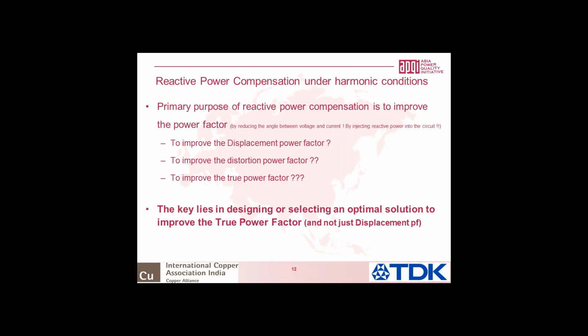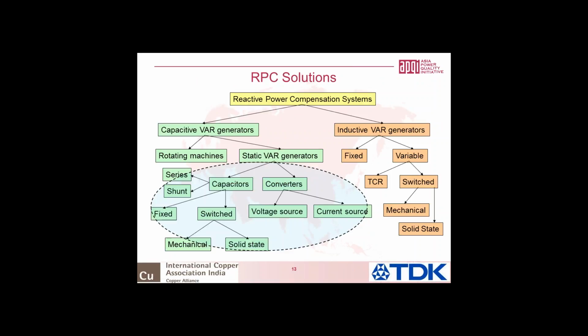As you would see, though they are linked, they can also be to some extent, or to a large extent, independently controlled, the displacement and the distortion power factor. So under harmonic condition, what I would submit, it's not just to improve the displacement power factor, it's important to improve the true power factor, and let's see how one can go about doing so. Before we get into a little more details of reactive power under harmonic conditions, I thought I'll just share with you some of the reactive power solutions.